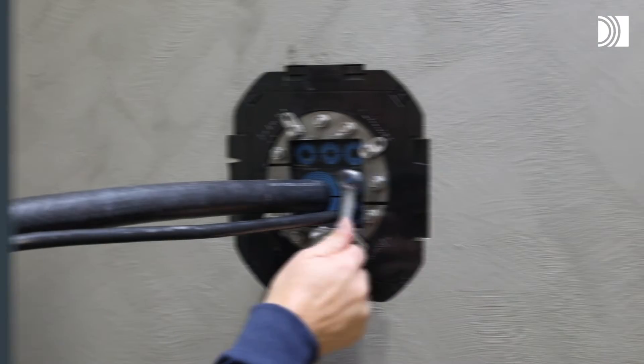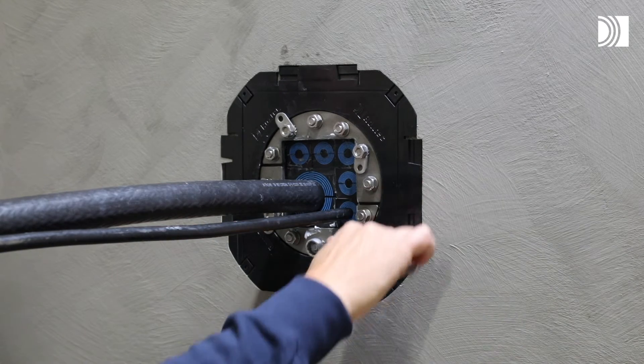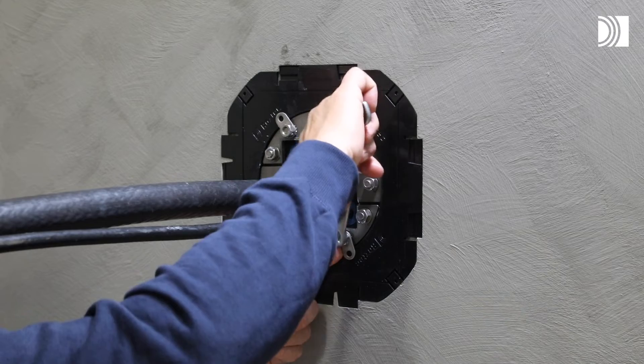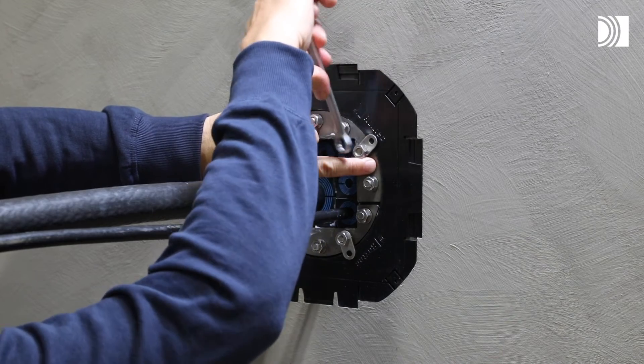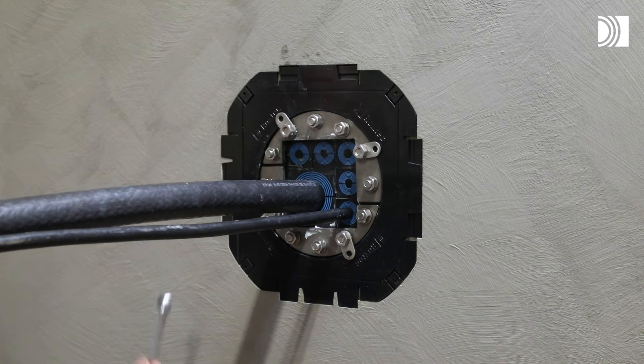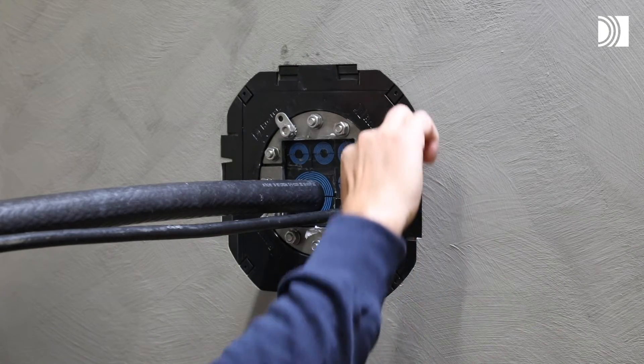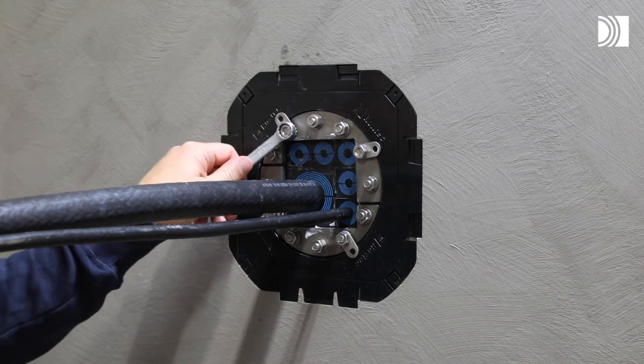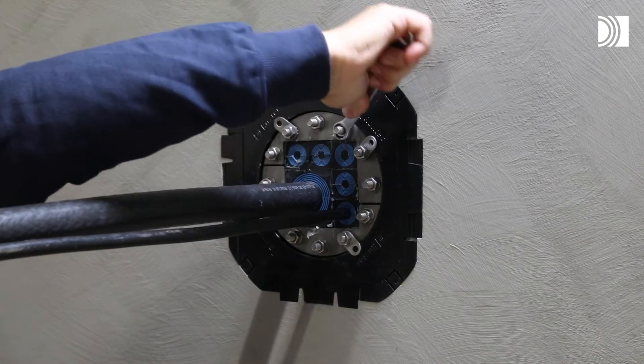Tighten the seal. Tighten the nuts crosswise in small steps. 4-10 mm of thread shall be visible after compression. Signs of good compression are the bolts are tightened similarly, excessive lubricant is visible directly after installation, and the rubber surfaces bulge and show convexity.